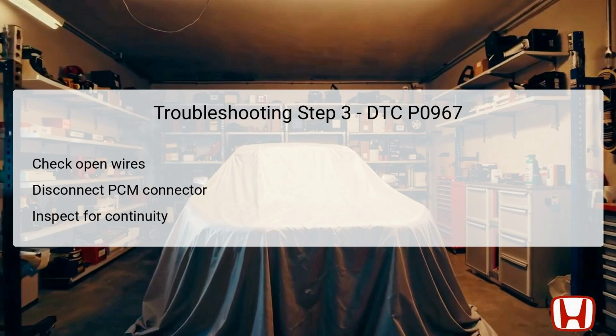Proper continuity must exist for both GND1 and GND2 LG wires to ensure a solid connection to ground. If continuity is confirmed, both wires are operational, and the next step would be to replace the PCM. Conversely, if there is no continuity, this indicates issues such as an open circuit, necessitating repairs to the wiring between the PCM and the ground, or fixing potential grounding problems at G101.